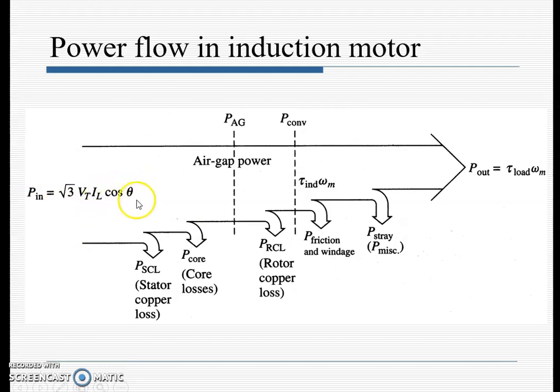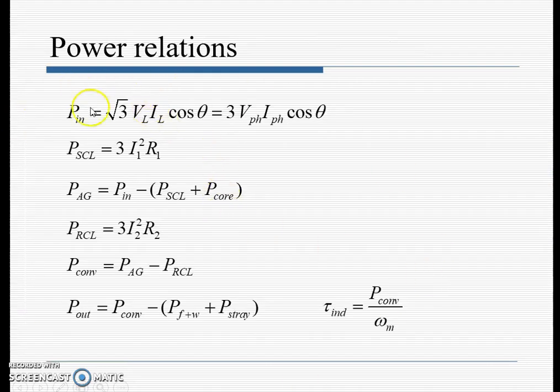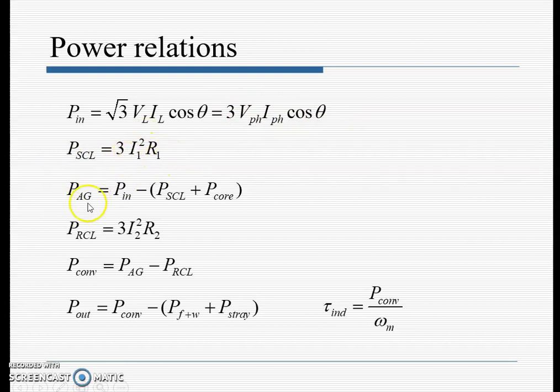The first losses subtracted are stator copper losses, then core losses, leaving the air gap power. Then rotor copper losses are subtracted. After friction, windage, and stray losses, the output power is torque × ω_m. The input power relations are: P_in = √3 · V_L · I_L · cos θ = 3 · V_phase · I_phase · cos θ. Stator copper loss = 3I₁²R₁. Air gap power = P_in − (stator copper loss + stator core loss).